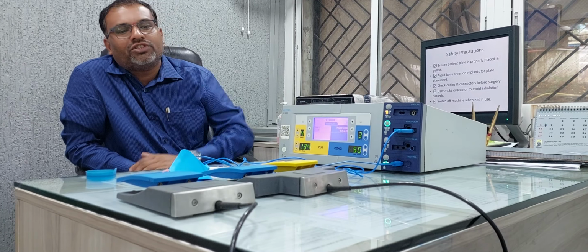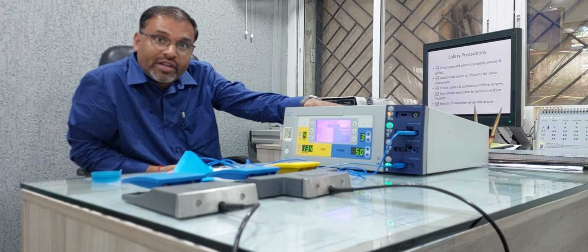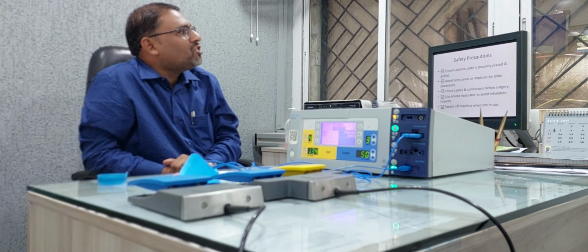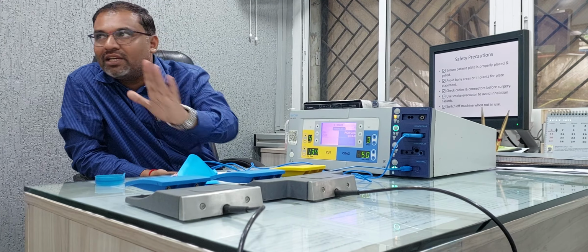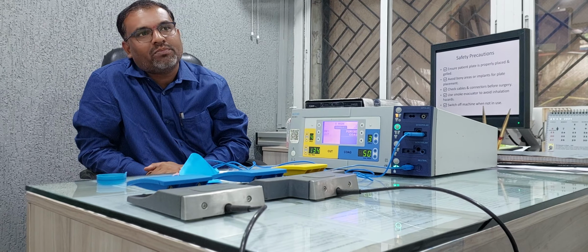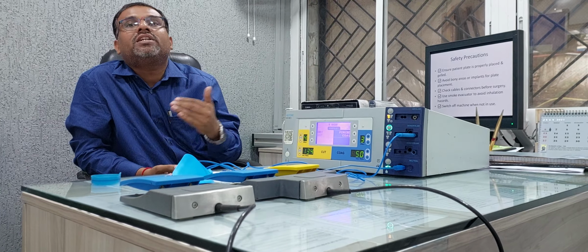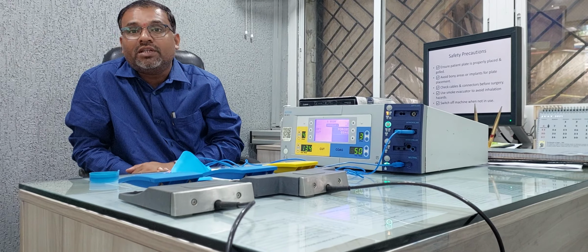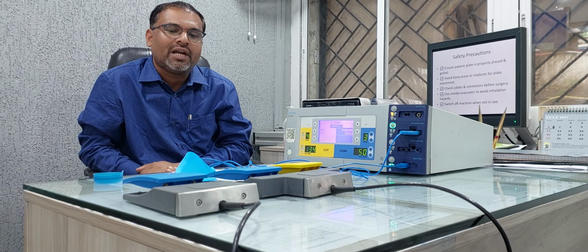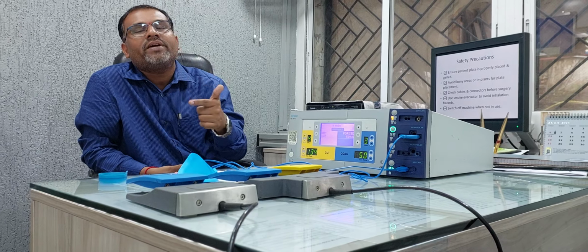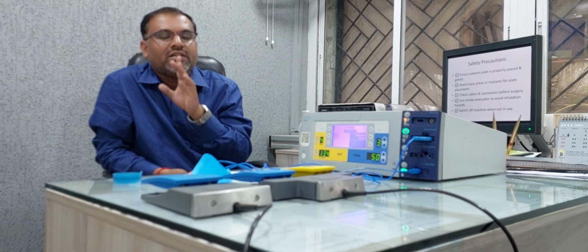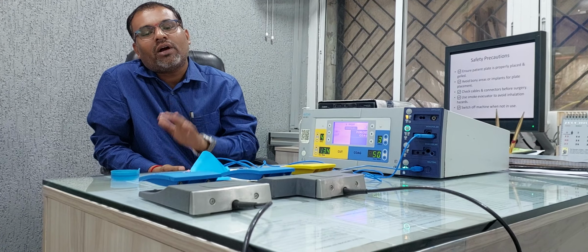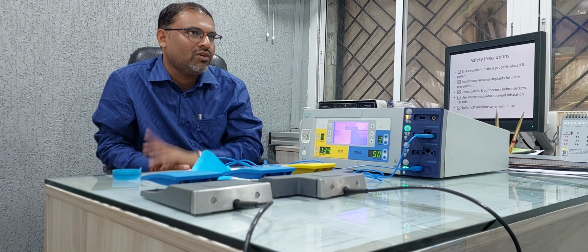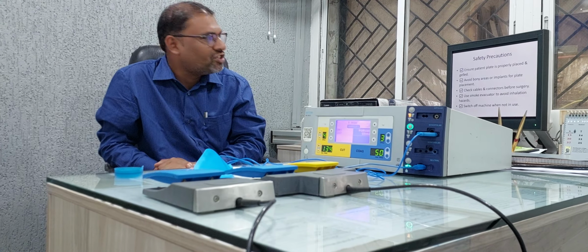What are the safety precautions you have to take during use of cautery machines? First of all, ensure the patient plate is properly placed or gelled. Sometimes in many hospitals, people are reusing disposable plates, and it can cause cautery burns to the patient. So always remember, if you are using reusable plates, that is okay. If the patient plate is disposable, you have to dispose of it after each and every use. So it will be good for the patient.